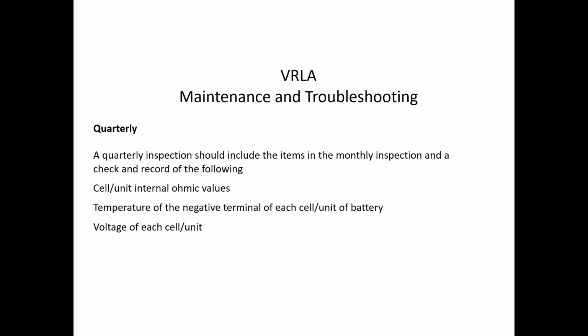And then also, if we're trending it, if we're saying, hey, this battery 2 months ago was an amp or less, and today it's 3 amps, and I know it didn't just come off of a discharge, you're not getting a recharge, I know I want to take a further investigation of that battery. So, like I said, quarterly maybe, if they could do that, I would absolutely recommend that they clamp that somewhere within that string or reading into that string, and not just depend on the rectifier.